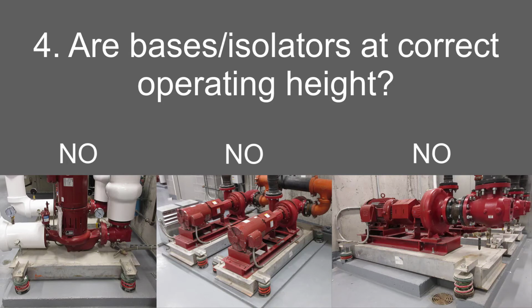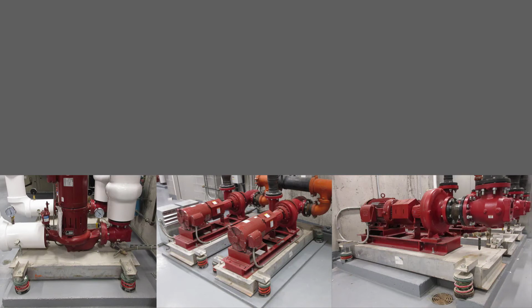I would ask the contractor to at least try to remove the debris under all of the inertia bases to ensure there is no short-circuiting, making spring adjustments as necessary to make sure the inertia bases are supported only by the spring isolators. Once that is done, it may not be necessary to raise the bases to the full 2-inch clearance if there are no noise issues below. However, it would be recommended practice to raise them as close to 2 inches as possible to avoid future problems.